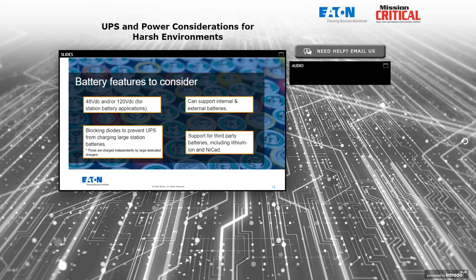So speaking of batteries, what features should we consider? What kind of battery voltage does the customer already have if they have a station battery? They may have invested heavily in a large 48-volt DC battery in a telecom application, and they simply want to hook the UPS's DC input to that station battery. Same thing at 120 volts DC for a lot of manufacturing and factory floor automation applications. The challenge there is that most modern UPSs benefit from having a higher DC voltage because it reduces the switching currents and increases the reliability and efficiency of the UPS. So in many cases, the customer may have a station battery available, but they end up deploying a dedicated battery at 480 volts or 240 volts DC, especially for the UPS. And the question is, can that battery handle the temperature extremes in that environment?